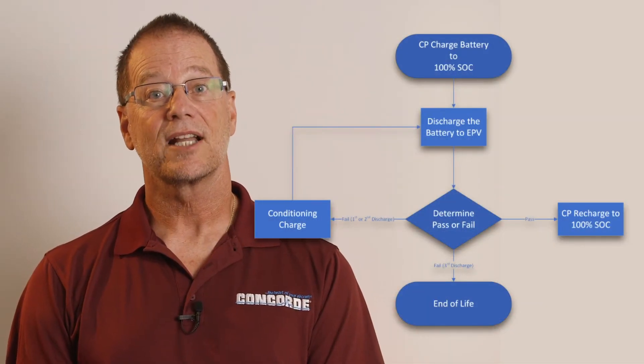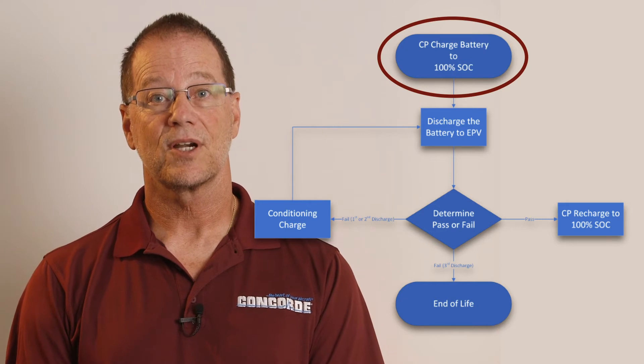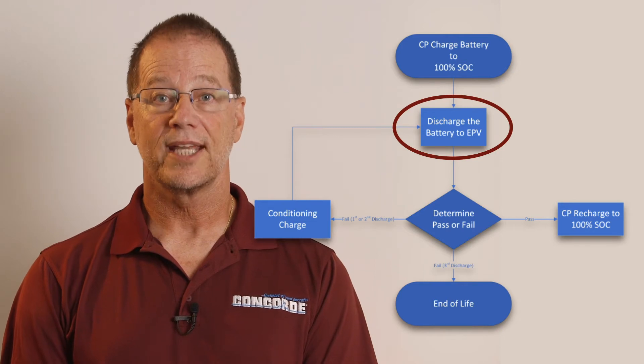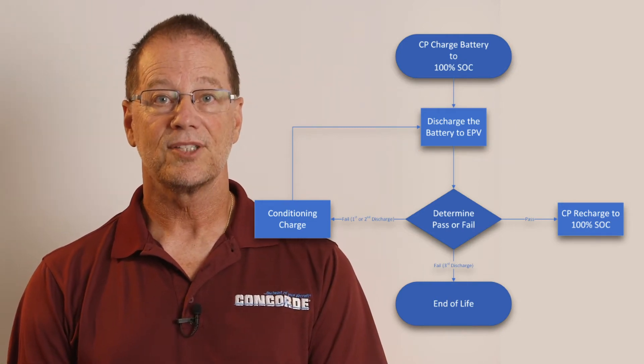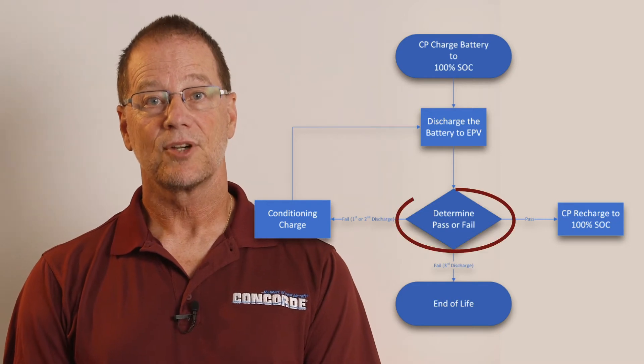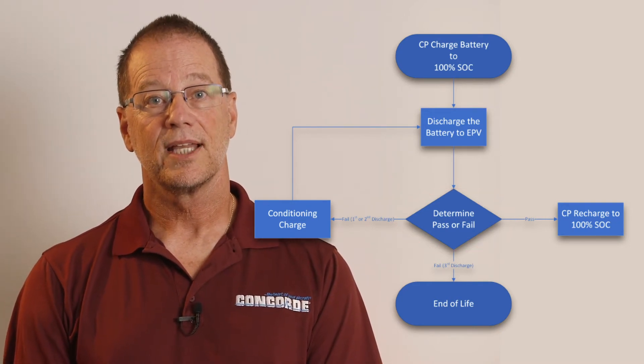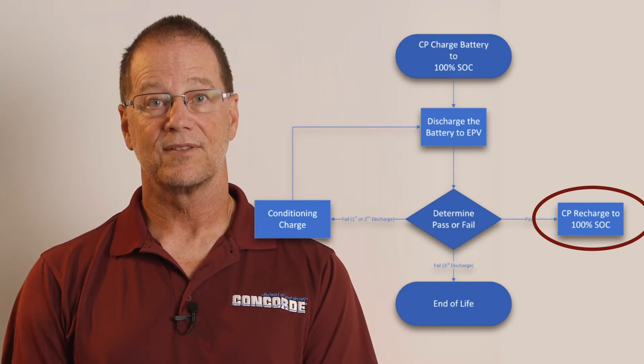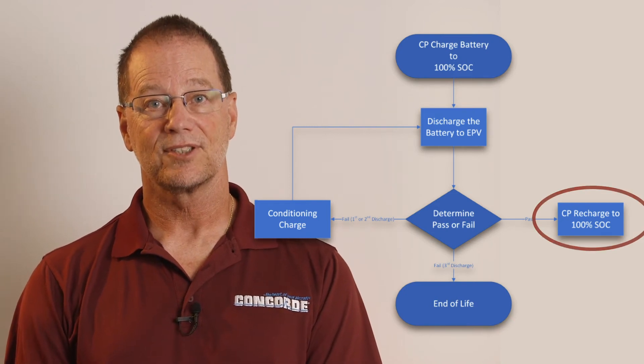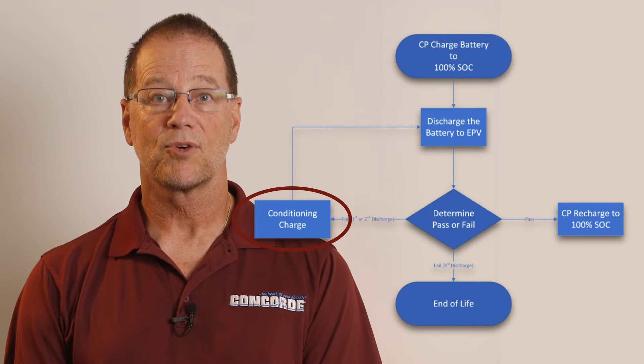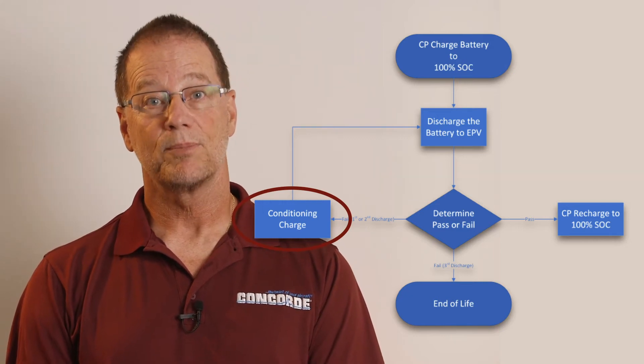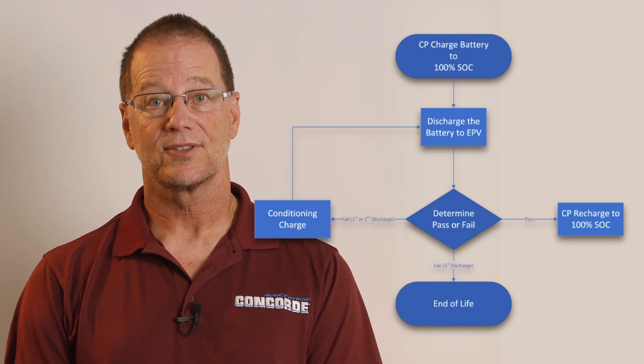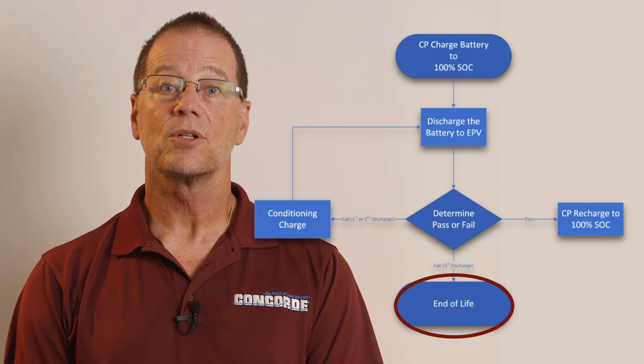The flowchart shown on the screen outlines the basic procedure for capacity testing. First, the battery is charged at constant potential to 100% state of charge. Second, the battery is discharged at constant current to the endpoint voltage. Third, based on the measured discharge time, determine if the battery passes or fails. If the battery passes, recharge the battery at constant potential to 100% state of charge so it is ready for aircraft installation. If the battery fails, perform a conditioning charge and repeat the capacity test. If the battery does not pass after three discharge tests, it is considered end of life and should no longer be used.